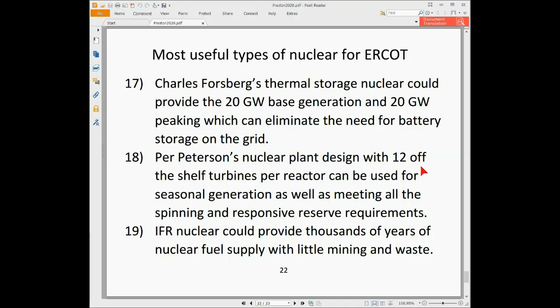Peterson's design is innovative in that he runs these turbines at only 100 megawatts, even though the turbines are rated at 240. So if you have a disturbance on the grid where you need extra power, during an emergency, you can inject gas into these turbines and they will ramp up instantly or almost immediately to higher power levels to serve the load until you have time to redispatch the generation.